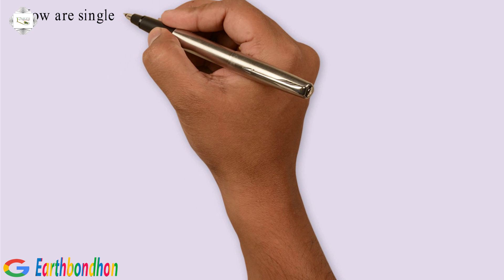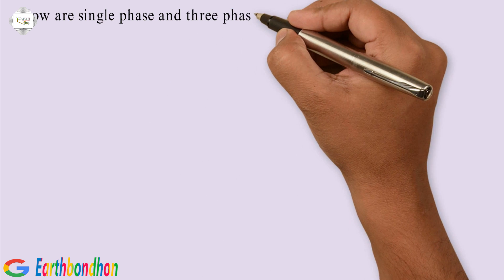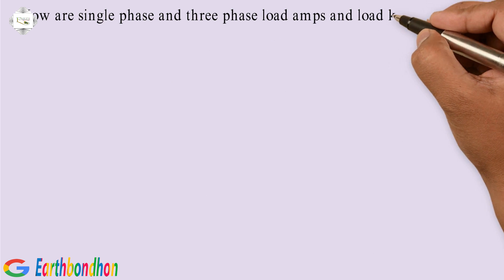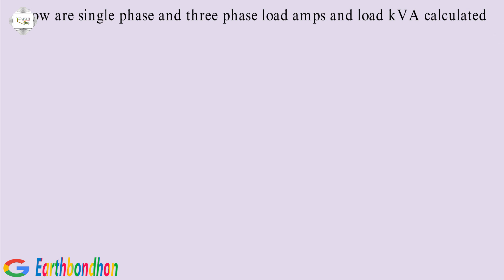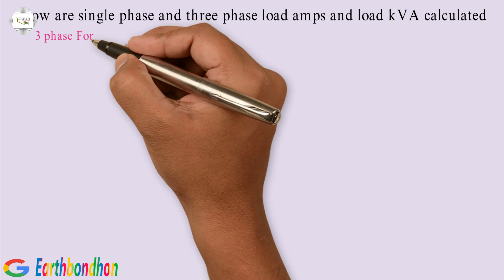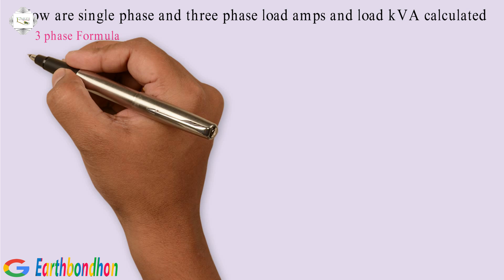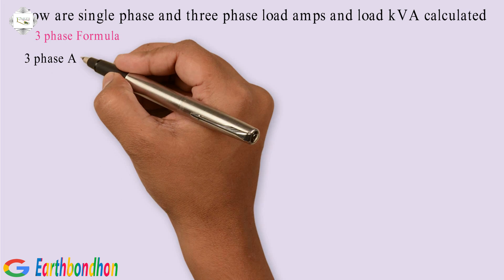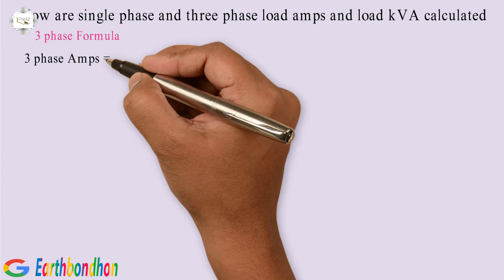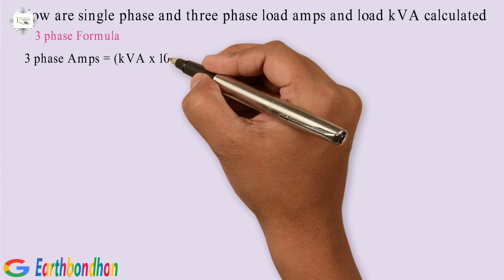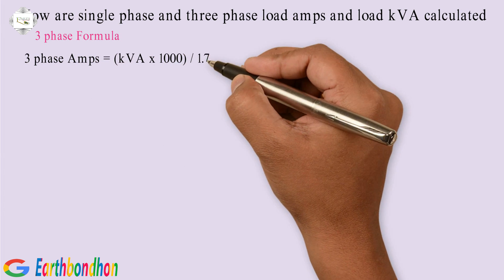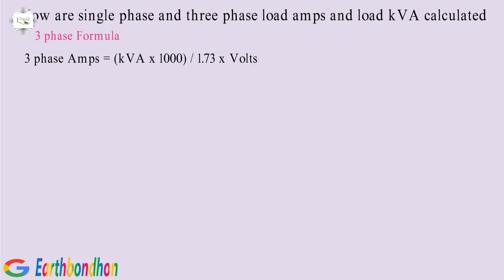Three phase load KVA calculation. Three phase formula: three phase amps equals KVA multiplied by 1000, divided by 1.73 multiplied by volts.